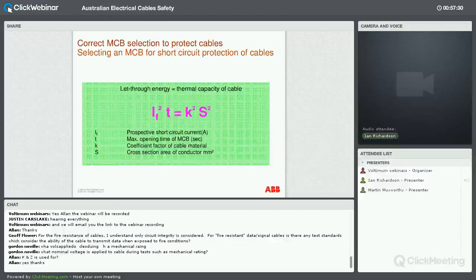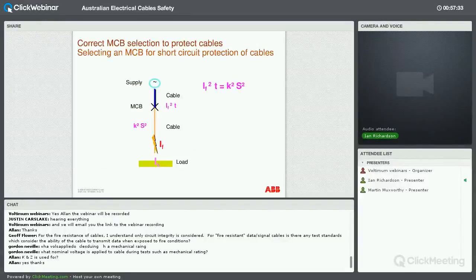you'll get the breaking of those currents at the appropriate time. There are some values that the cable manufacturers will be looking at when we're talking about short circuit values, and if we have a very, very high current flow for a very short period of time, the cable is actually designed to withstand this, because they're designed to cope with a short circuit, provided that the short circuit is cleared in a reasonable time. So you will get a fast injection of heat into the cable, but because the circuit will be cleared by the protective device, the cable will be allowed to cool and you won't suffer any sustained damage.